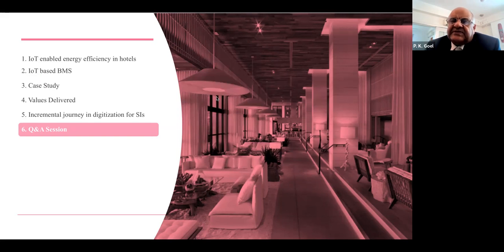Now, can small subsystems be deployed on rooftops for just doing COP of chillers? That's a very, very small thing - basically a flow rate through the chiller or chilled water system, inlet-outlet temperature sensors that give the kilowatt of cooling taking place, and some monitoring systems on the electrical switchboard to monitor kilowatt consumption at that point, which will announce the COP. Somehow, it's such a simple thing, but it has not been integrated by the manufacturers on their chillers. So what are your thoughts on it?